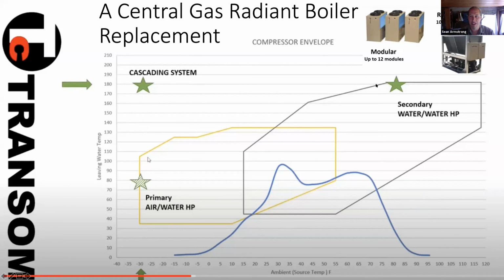We're trying to get up to 180 Fahrenheit for space heating boilers. So if you're in New York City replacing a boiler for an apartment complex that heats the radiators, you'd use a second heat pump to get the job done. You'd raise the water to, say in this case, 80 degrees Fahrenheit from negative 30, and then that second heat pump would raise it from 80 up to 180 Fahrenheit. That's the technical phrase, a cascading system—one cold climate air source heat pump, then a water source heat pump to concentrate the heat in the recirculating water and get it up to 180, or 160 to 180, which is what a radiator might use.